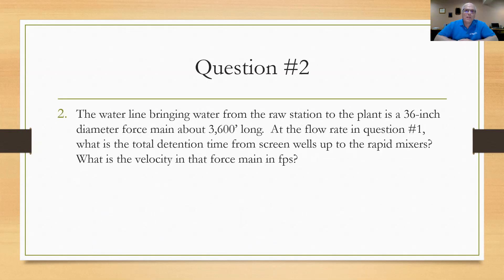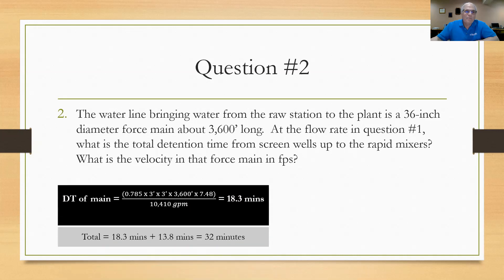Question number two: The water line bringing raw water from the raw water station to the water treatment plant — about 3,600 feet away — is a 36-inch diameter force main. At the 15 MGD flow rate from question one, what is the total detention time from the screen wells up to the rapid mixers? The detention time of that force main was calculated using 0.785 times diameter squared times 3,600 feet, converted to gallons and divided by the flow rate, giving 18.3 minutes. Adding that to the 13.8 minutes gives about 32 minutes total detention time.